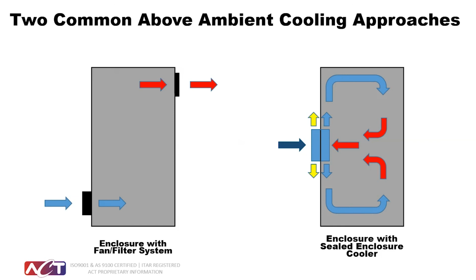Now let's look a bit deeper into above ambient cooling options. The diagrams shown here illustrate the air movement of the two cooling approaches shown. A fan filter system is shown on the left. Outside air, shown here as the blue arrow, is moved through a filter and into the enclosure where it circulates among the components and gathers waste heat. The red arrow on the diagram represents heated air, which leaves the enclosure at a second opening in the wall of the enclosure.